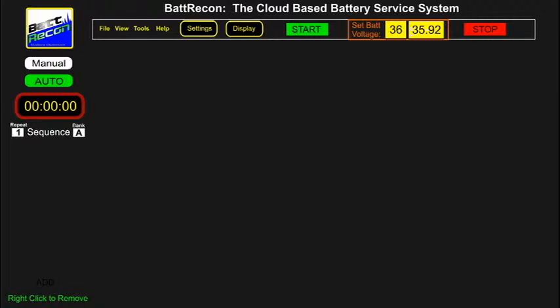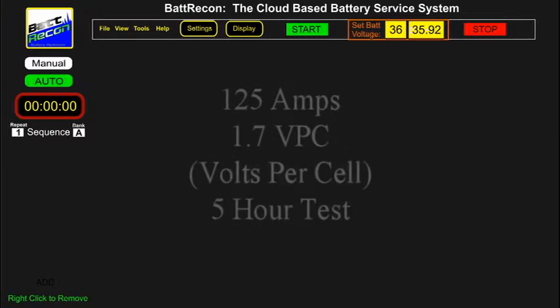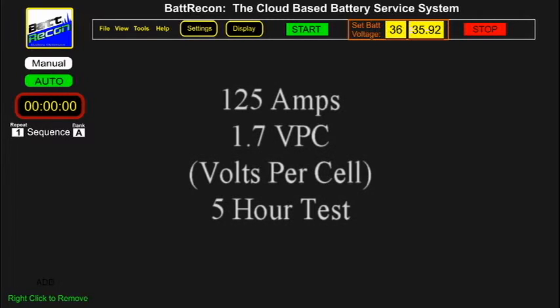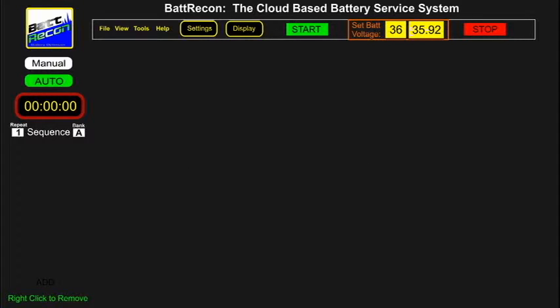Let's first start with a manual mode of operation. We will select a BattRecon discharge device to discharge-test the battery at 125 amps until the calculated volts per cell, or VPC, reaches 1.7. We are testing to see if the battery will last for five hours at this discharge rate.